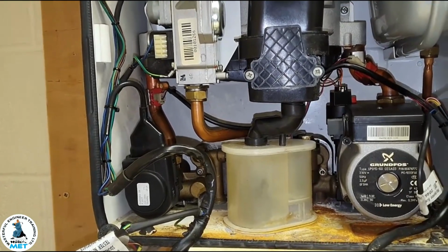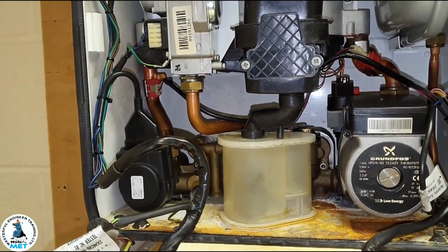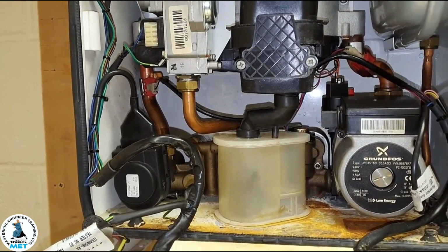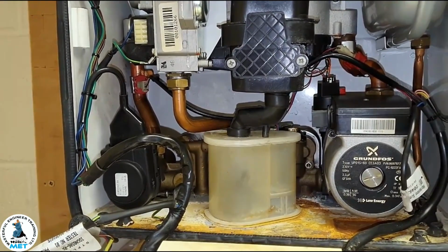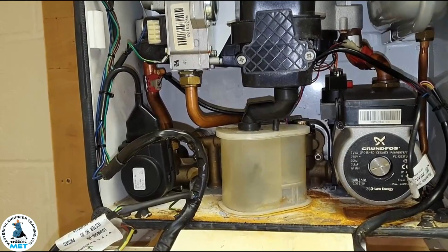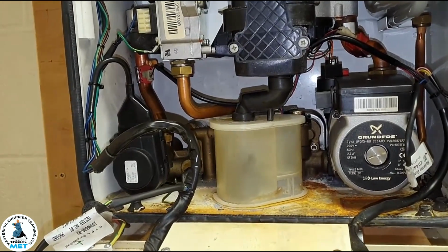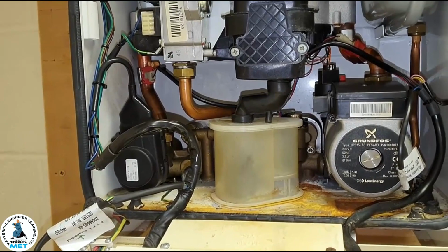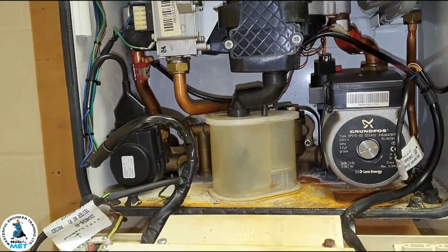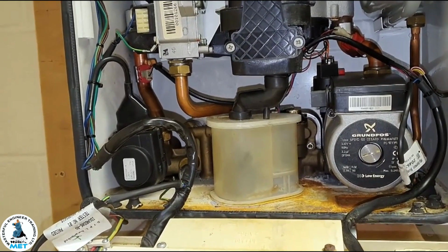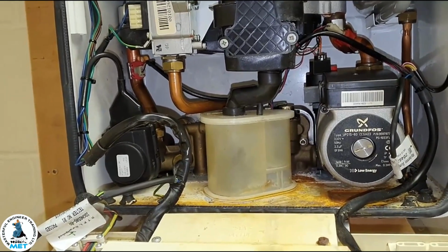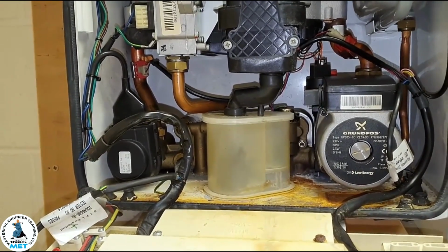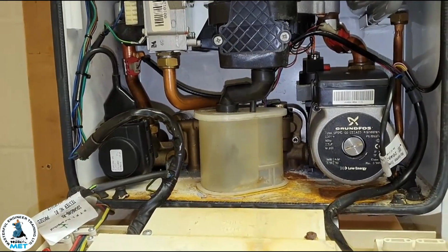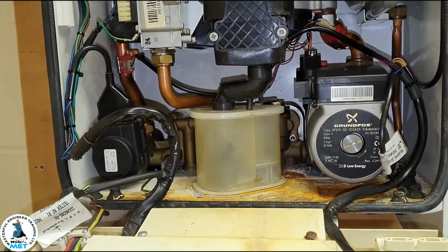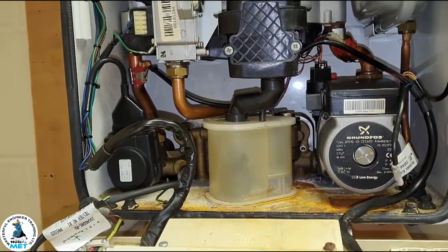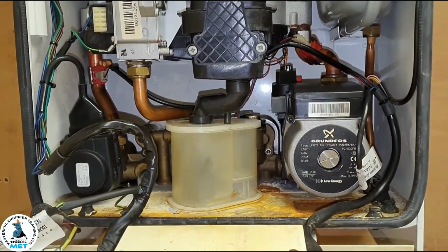You could have the internal or external filling loop letting water into the system, making the pressure go up. If you've got an external filling loop, you can disconnect it altogether so it's not connected, and it still continues to rise - pressure goes up after half an hour. Then the only other way is the hot water heat exchanger. You've got a hole in it.